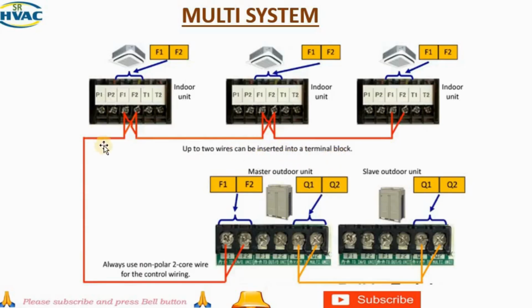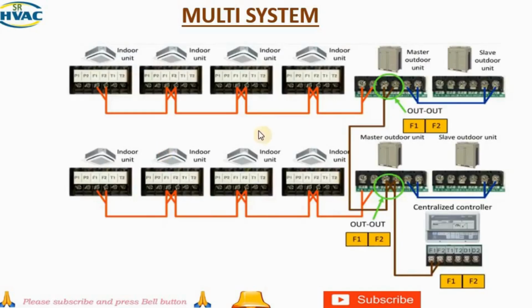You can see this is how looping is done between the indoor unit and the outdoor unit with a multi system. Okay, this is a master outdoor unit and this is a slave. I hope you know what is a master outdoor unit and a slave outdoor unit. Okay, if you want to know which is master and which is slave, you can check Q1 or Q2. Okay, which one is connected with F1, F2 and Q1, Q2. We will see all the centralized system also, how it is connected. You can see these are the different systems. Okay, this is a multi-system also. You can see these are the different outdoor master and slave.